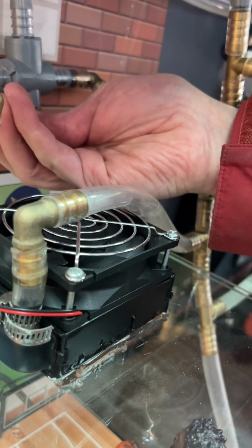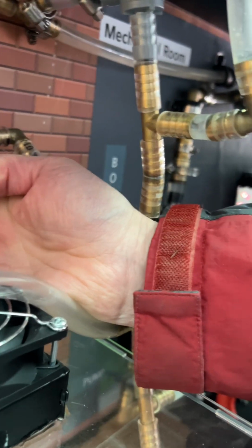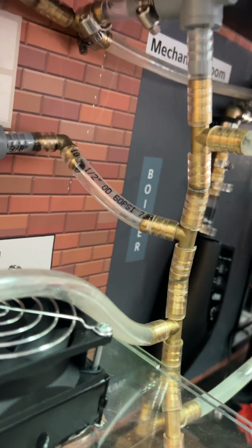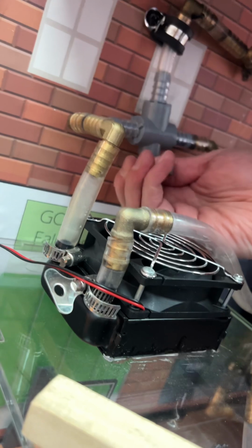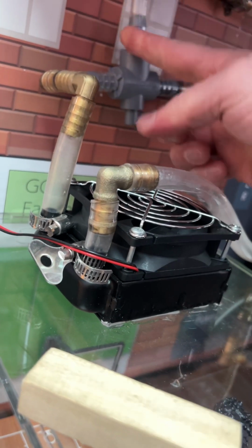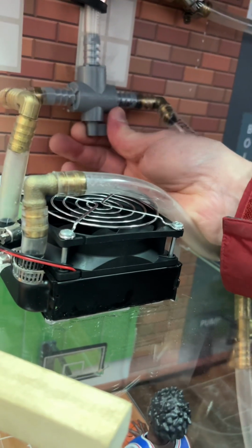So this valve is a three-way valve, and it can be turned to either have the water coming into this unit go through the coil, or it can be diverted the other way, and in that case the water will bypass and skip this coil and just continue on around the loop. So in that case, the gym doesn't get heat or air conditioning.